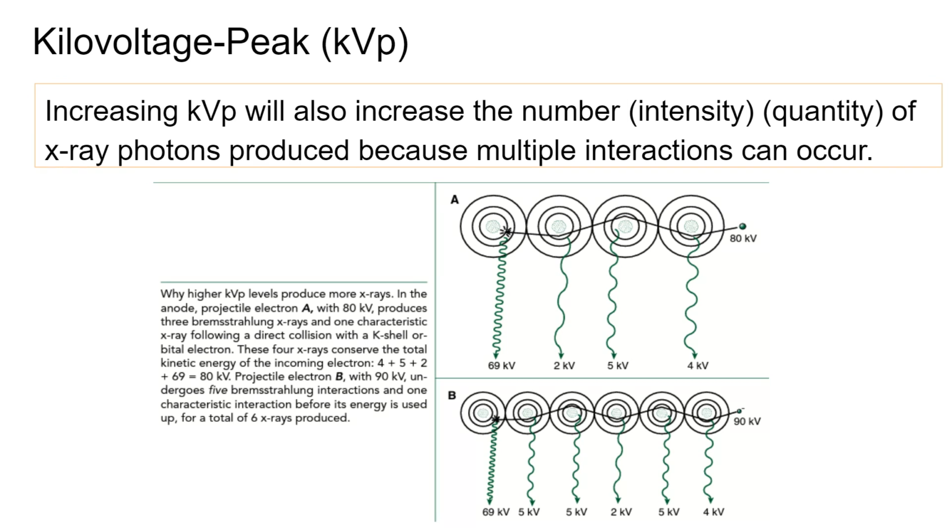So if you're doing an abdomen or lumbar spine, you can't use 50 kV. Even if you jack up the mA and the time as much as it'll go, you'll have this. Woo! And it's all right there. Just there. Didn't really penetrate anything. Right? Not enough to hit the spine and show you what's going on with the spine and be absorbed differentially by the different parts of the spine to give you different shades of gray. Not 50 shades of gray.